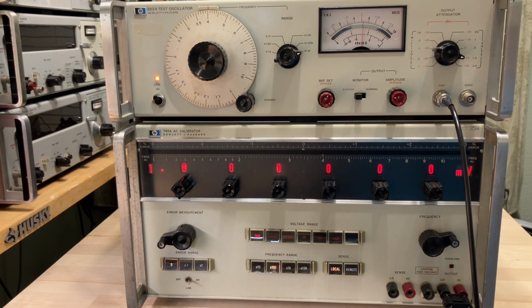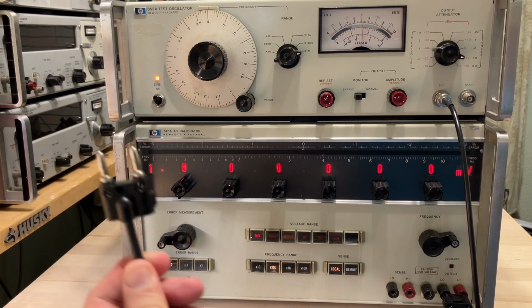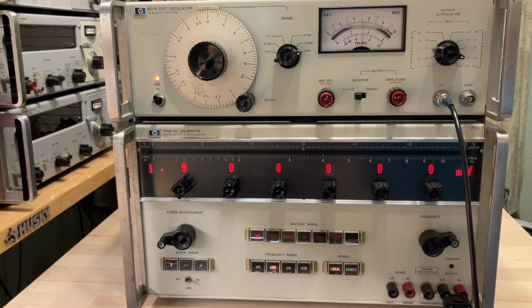Apply that voltage to the input of the meter through this banana cable that I have connected to my output over here. That goes to the input of the 400H under test, and I make the adjustment to make 1 millivolt full scale reading on the 400H instrument.